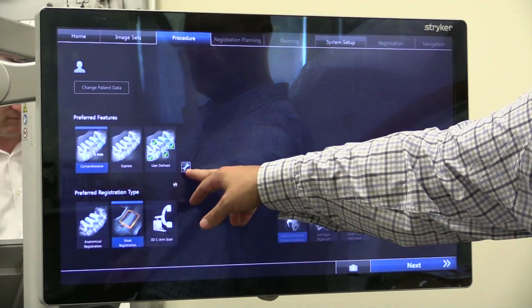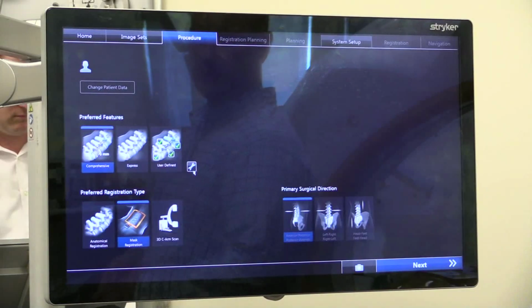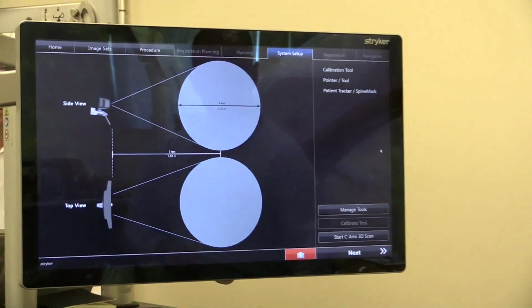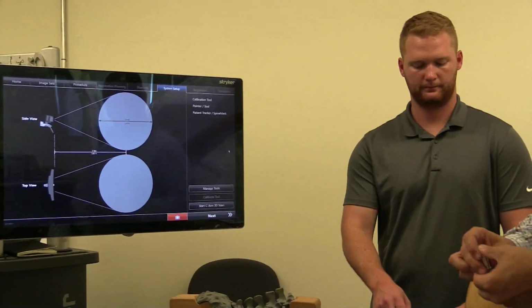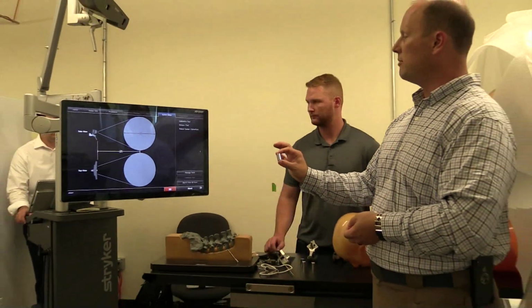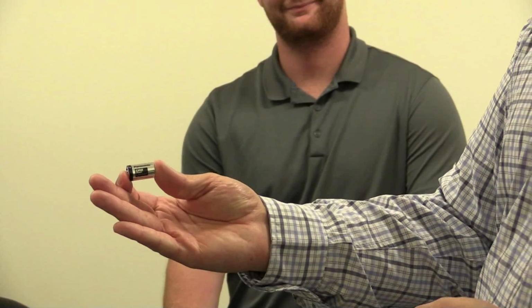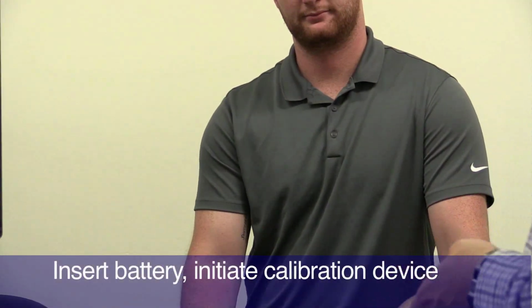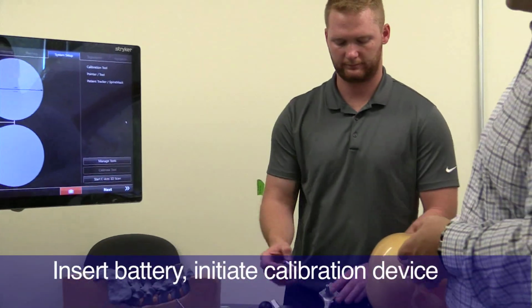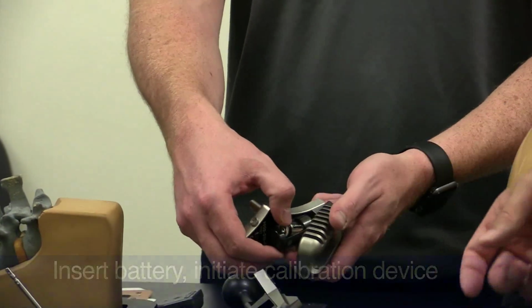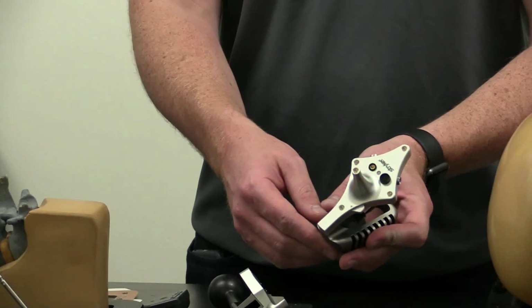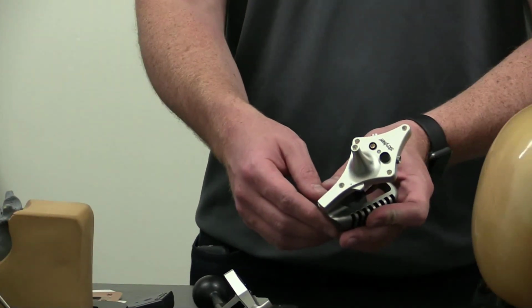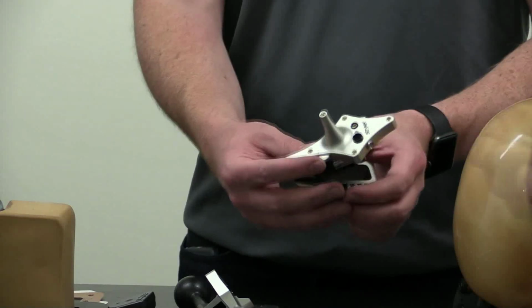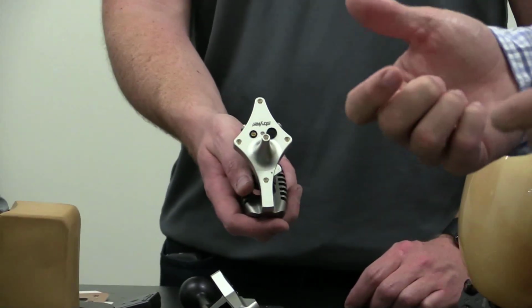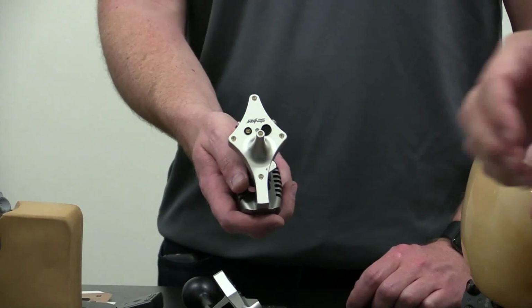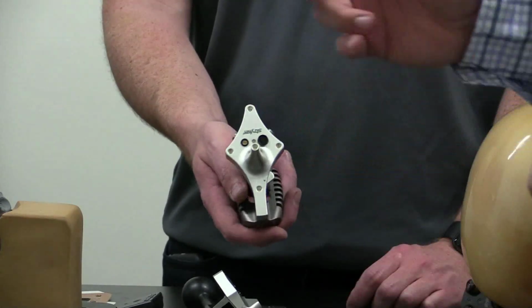We can modify it here in the toolbar if we wanted to change any of the functions and features. Alec is going to be our scrub tech that would be turning on the instrumentation. The active instruments are actually powered by a 3-volt battery that comes sterilized. To initiate the instrument, we're just going to place the battery into the instrument, and once it slides in, he'll turn it and you'll see a green light come on as an indicator. The light should come on, hold on for about a second, and then flash off. It has an indicator built into it so that you know if there's anything going on with the instrument. This is giving you the okay that the instrument has officially powered up.